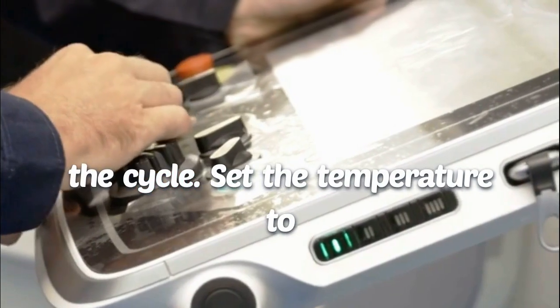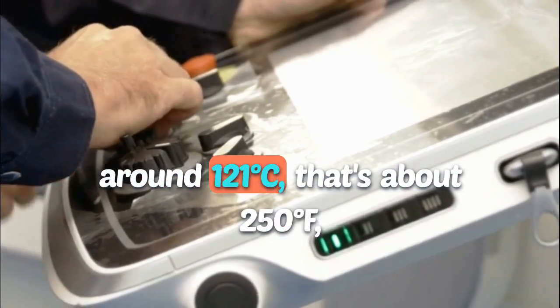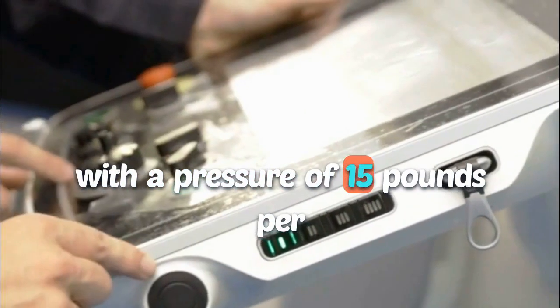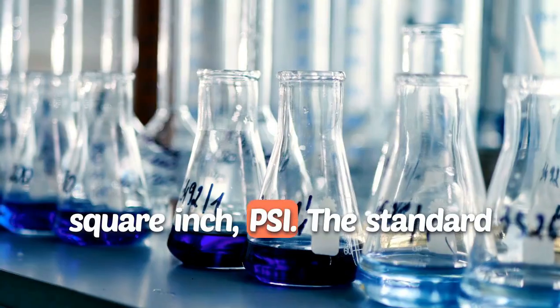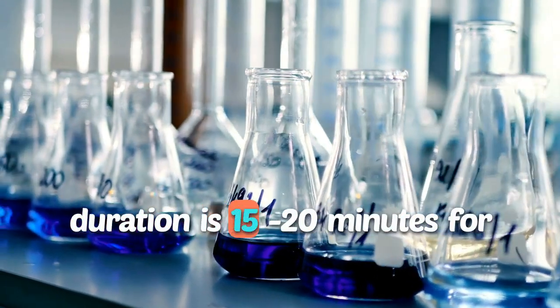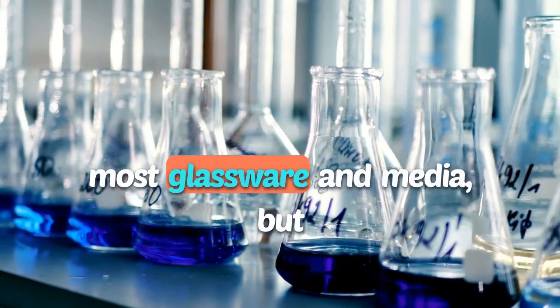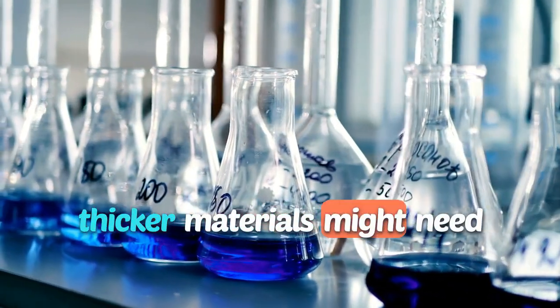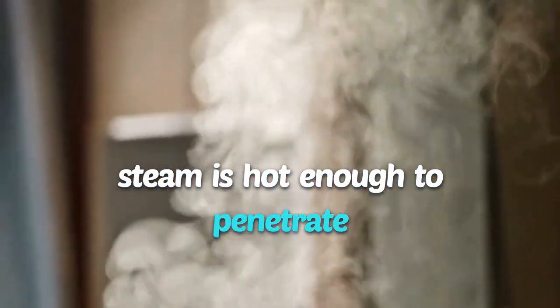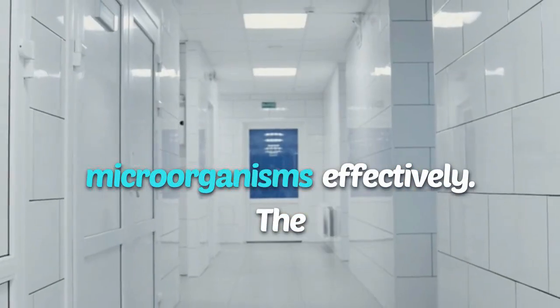Setting the cycle. Set the temperature to around 121 degrees Celsius, that's about 250 degrees Fahrenheit, with a pressure of 15 pounds per square inch, PSI. The standard duration is 15 to 20 minutes for most glassware and media, but thicker materials might need longer. These settings ensure the steam is hot enough to penetrate deep into any material, killing microorganisms effectively.